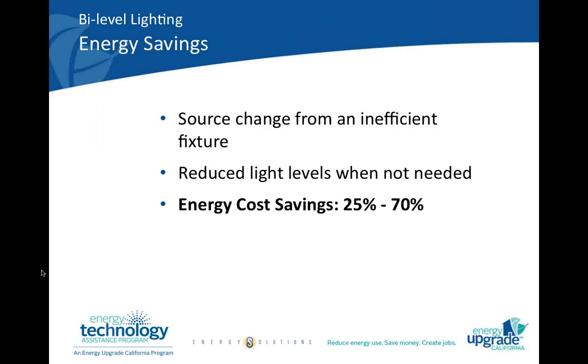So the energy savings that can be achieved from installing this bilevel lighting technology are really twofold. As I've discussed, first, by upgrading our lighting technology from older, inefficient lights, such as HID lights, to newer, high-efficiency lighting, such as LED, high-efficiency fluorescent, or induction fixtures, in most cases you can cut the wattage considerably while still maintaining the existing light levels. The second portion of the savings comes from the reduced wattage that occurs when the fixture operates in low power mode when nobody is present. And this can typically add another 15 to 25% onto the energy savings. So the total potential energy savings for these types of projects is quite wide. It can be anywhere from 25 to 70% depending on the project.